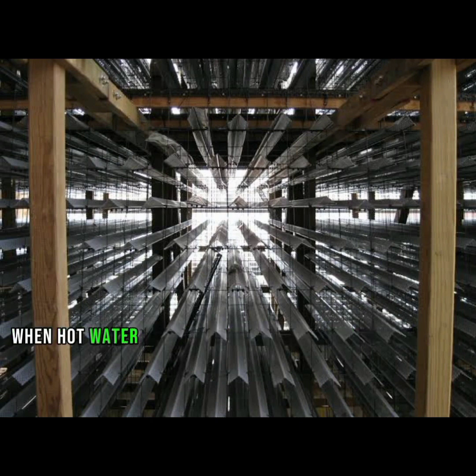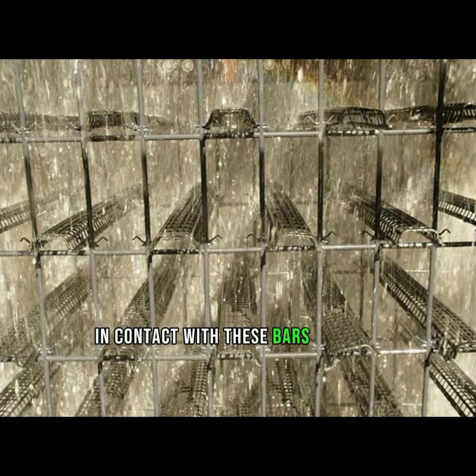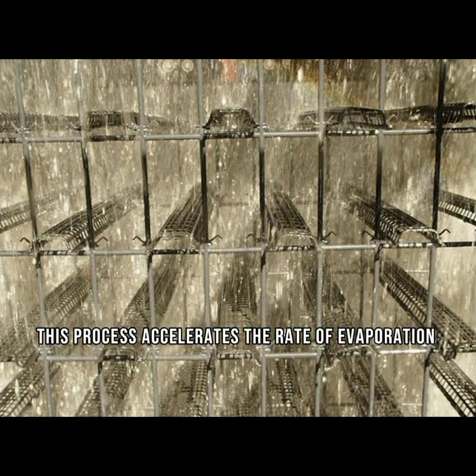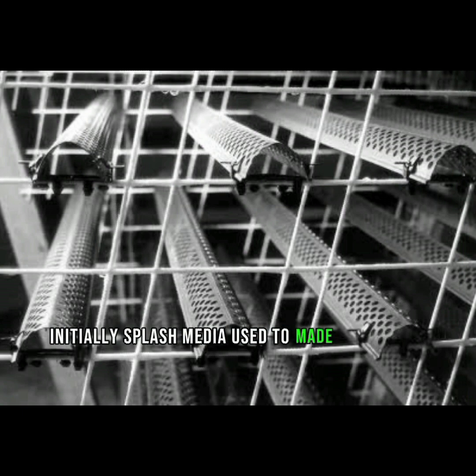When hot water in industrial water cooling towers comes in contact with these bars or slats, it breaks down into tiny particles. These small particles enable increased contact between the water and the air found within the atmosphere. This process accelerates the rate of evaporation and cooling. Initially, splash media used to be made using wood. However, now manufacturers are using more modern designs by adopting PVC. It allows a higher rate of heat transfer.